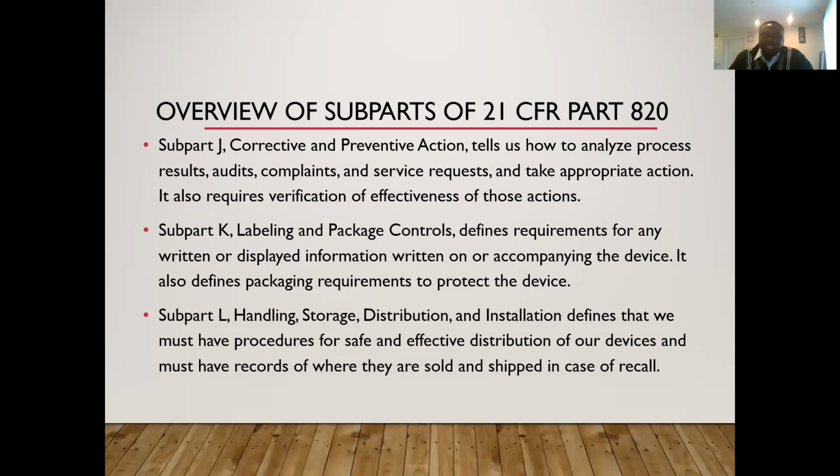And if you have procedures in place for handling, storage, distribution, and installation, these things will be kept. It will help alleviate these issues that come within shipping and handling of our medical device, and you must have records for where they are sold and shipped in case of recall. Where there are recalls, products are being called back to the company, brought back to the manufacturing floor. So there's the need for traceability.